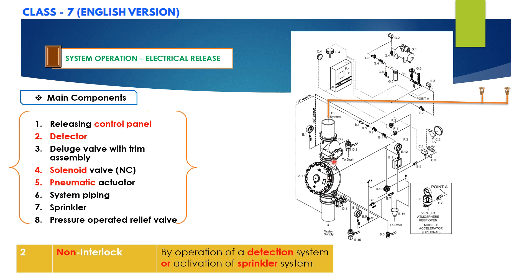In a fire condition, when the detection system operates, the system control panel energizes the solenoid valve to open. Pressure is then released from the priming chamber faster than it is supplied through the restricted orifice. The deluge valve clapper opens to allow water to flow into the system piping and alarm devices. When a sprinkler head opens, water will flow from the system.